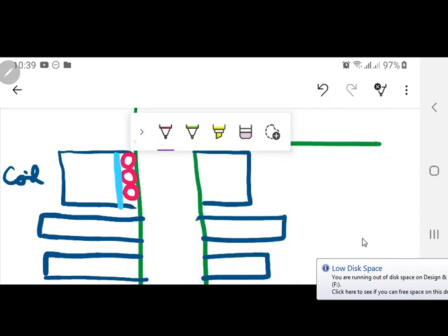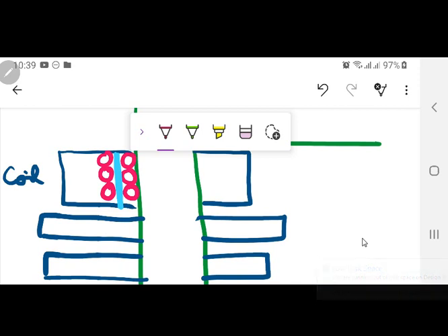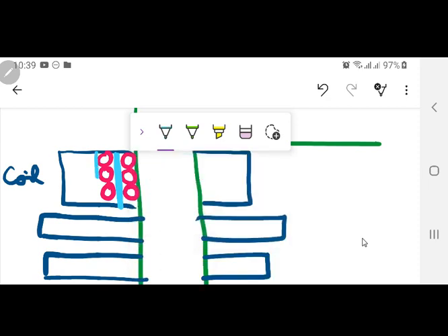Now 832, they have to be arranged in such a way that you are going to have layers. Now this red conductor already has a covering on it. Remember, it already has a 0.2 mm dual paper covering. But when you are going to increase insulation, you are going to put another insulated layer because they are layers. And it is 11 kV. If this were low voltage, no problem. This is 11 kV. Okay? So I have to put a layer of insulation. So this layer of insulation in each packet is going to be there.